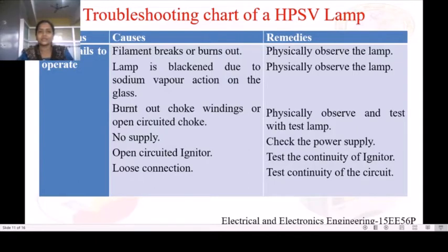This table shows a troubleshooting chart of a high pressure sodium vapor lamp set. In this chart, the common problems that occur in a high pressure sodium vapor lamp set, the possible causes for those problems, and the remedies are suggested. First problem, lamp fails to operate. For this problem, the possible cause may be that the filament breaks or burns out. For this cause, we need to physically observe the lamp for any breakage in the filament or for any discoloration.